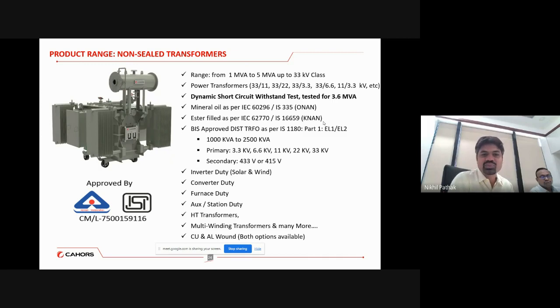So why has the non-seal transformer been named as the conservator type transformer? Because a seal type of transformer is there. So that is the reason it is a non-seal transformer. This is also a terminology adopted in the Bureau of Indian Standards, framing the different technologies while building the specification. And this range we are not encouraging for smaller capacities. However, minimum 1 MVA we are proposing for offering these non-seal transformers, up to 5 MVA, 33 kV class.